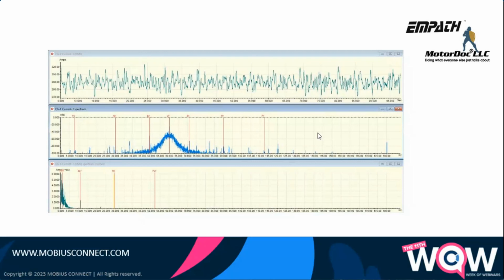So here's a typical application. This, again, is a belted application with a fan and turbulence. So in ESA, this is turbulence. Turbulence piles up around my line frequency, so that leaves everything else wide open. Now, if I'm doing vibration, turbulence ends up elsewhere, like around my blades or around blade frequencies, around my RPM frequencies. That's one of the benefits of ESA, is it pulls it away from that. It does mask a few things down here, but usually those peaks are right on top of the turbulence in any case. So it'll be there, but it'll be buried a little bit.